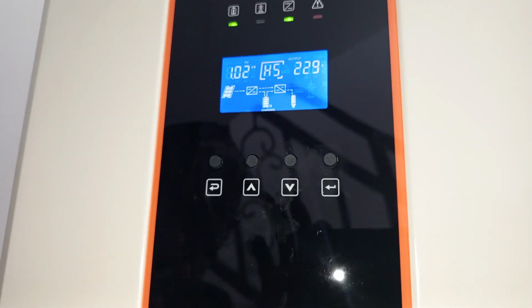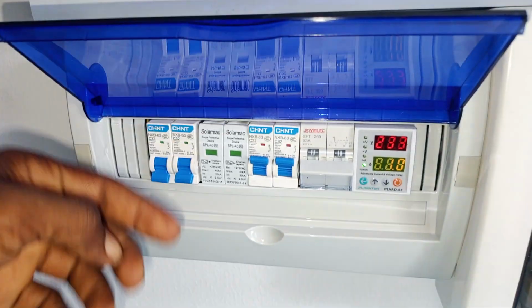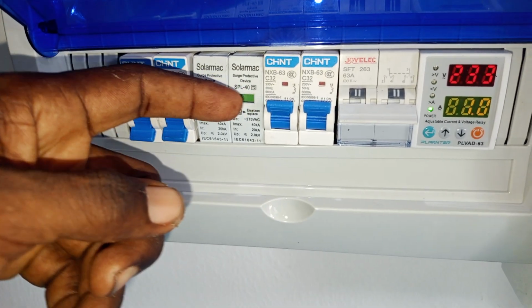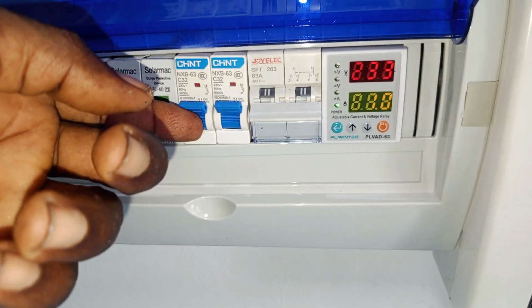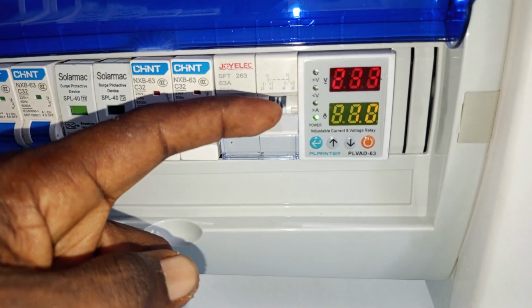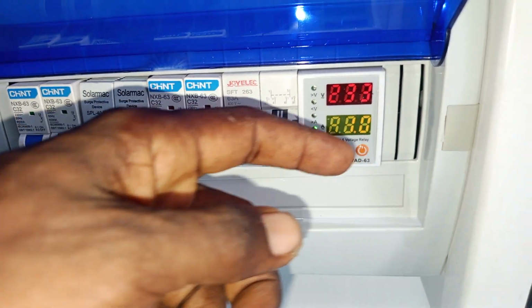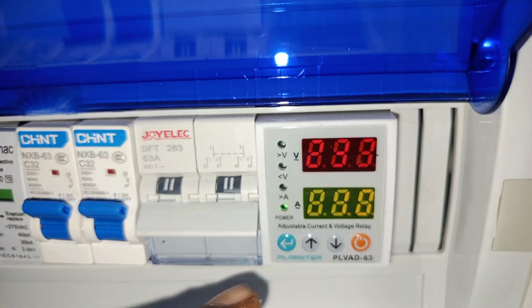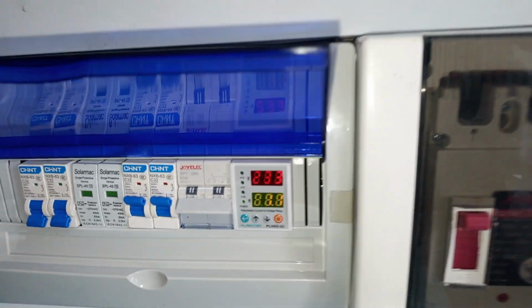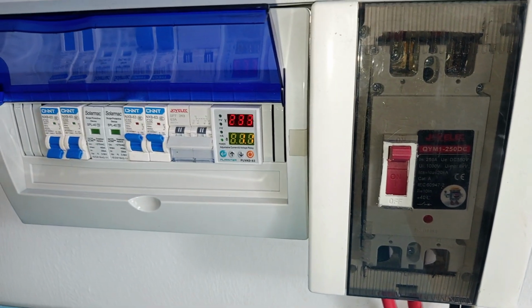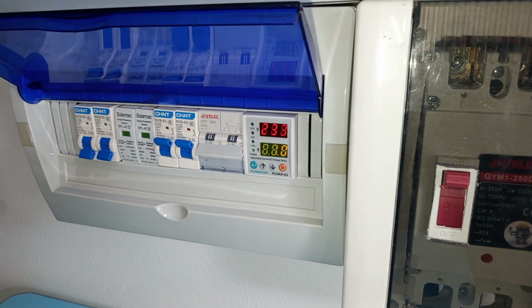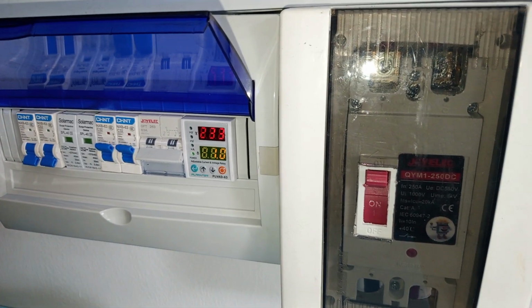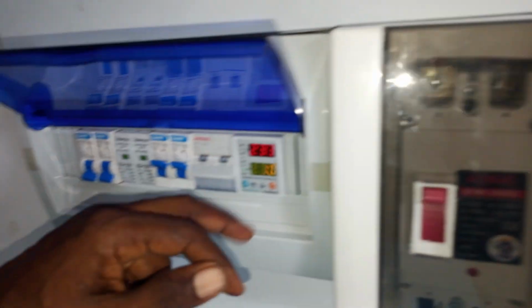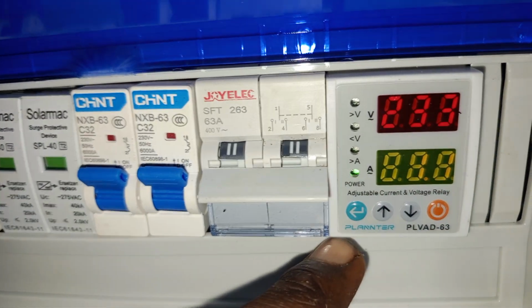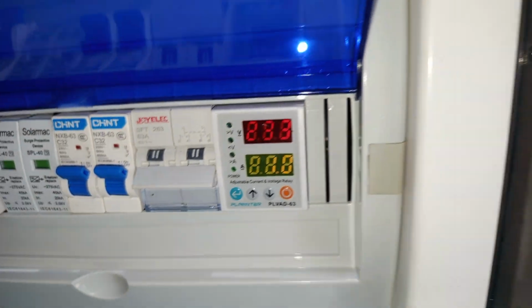We have our own protection systems here. This one protects the input. This one is a surge protector for the AC aspect. Then we have this one for the output breaker. This one is like a bypass and also a changeover. Then this one is a voltage regulator, which we installed to monitor the load, because we discovered that they had a water heater inside, and during load separation, the electrician did not show up as expected. They did the wiring in a way that we cannot separate the wires, so we did voltage monitoring here. So whenever they put on that water heater, this system cuts off, except maybe they go on bypass, which is using direct source from NEPA.